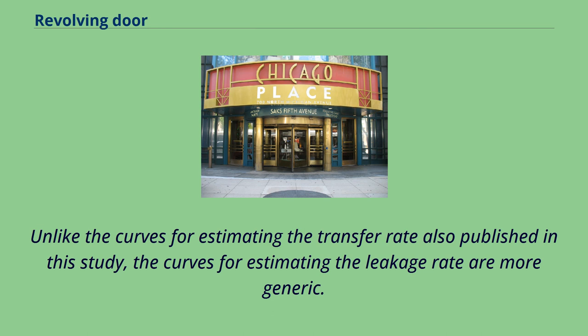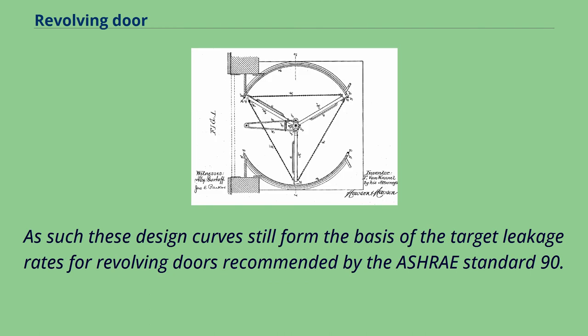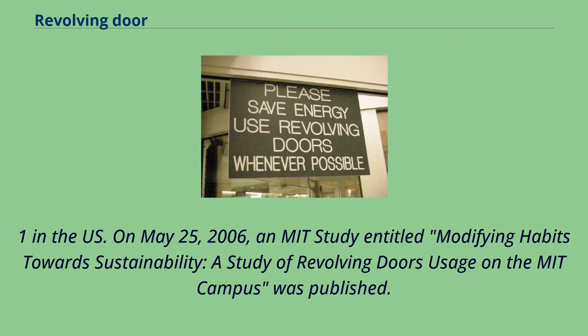The second study produced design charts for estimating the leakage rate through a revolving door. Unlike the curves for estimating the transfer rate also published in that study, the curves for estimating the leakage rate are more generic. As such, these design curves still form the basis of the target leakage rates for revolving doors recommended by the ASHRAE Standard 90.1 in the U.S.